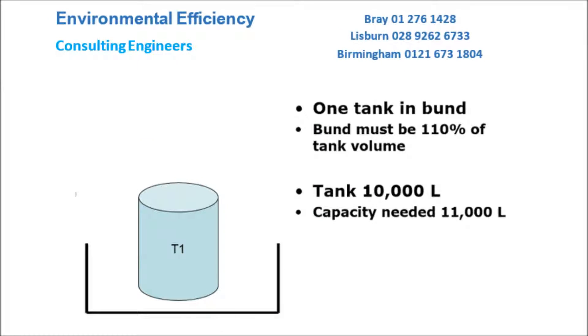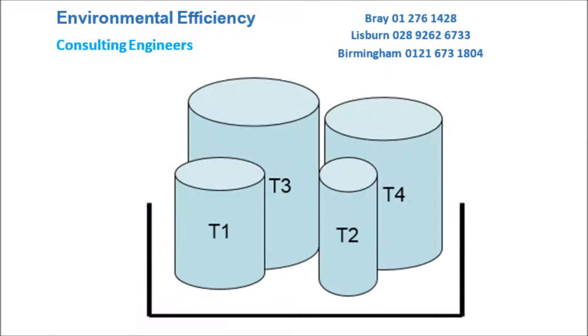Bunds have to have sufficient capacity to contain the volume likely to be released in an instant. For a single tank, the general rule is that the bund must contain 110% of the tank volume. Where there is more than one tank in the bund, the general rule is more complex and this will be covered in a later video.